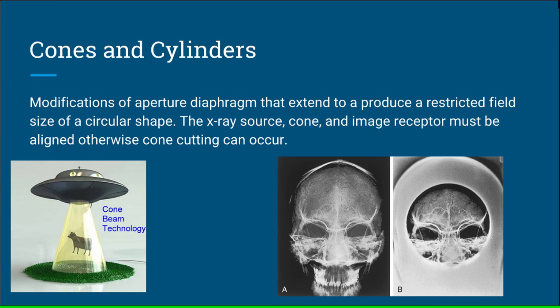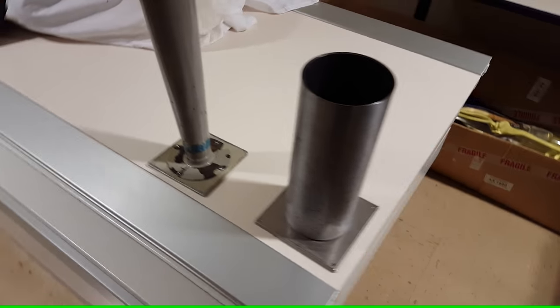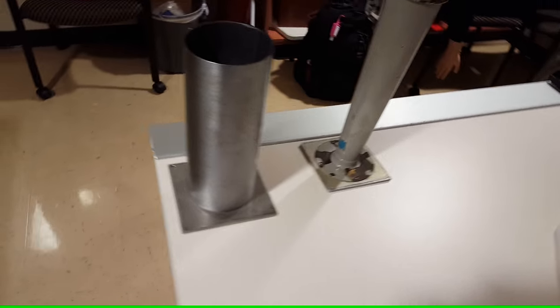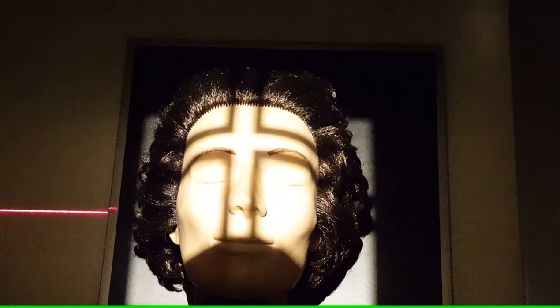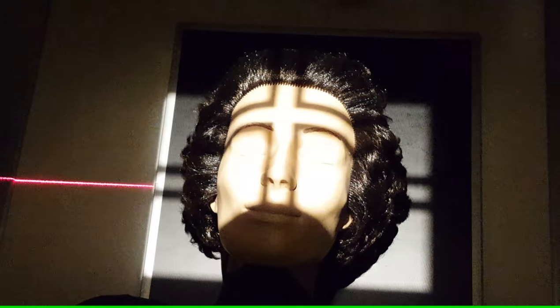Cones and cylinders are modifications of the aperture diaphragm that extend to produce a restricted field size of a circular shape. The x-ray source, cone, and image receptor must be aligned, otherwise cone cutting can occur. Today, cones and cylinders are reserved primarily for examination of selected areas such as sinuses. Radiographic cones and cylinders produce restricted useful x-ray beams of circular shape. The use of cones funnels the beam to the anatomy of interest, therefore reducing scatter radiation and improving image contrast.